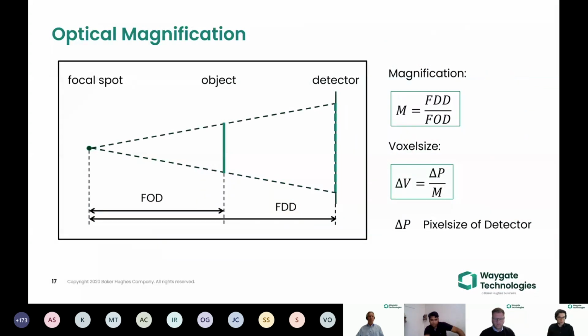So, one or two more slides on the metrology background. This is now more for the CT background, and then we will start with our technical solutions. One thing that I want to explain really quickly, because it's very important to understand why we're doing what we're doing with our machines, is the concept of optical magnification. Our CT scanners, and pretty much every CT scanner on the market, use optical magnification.